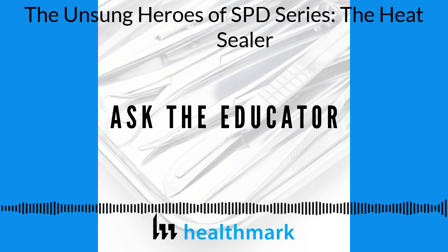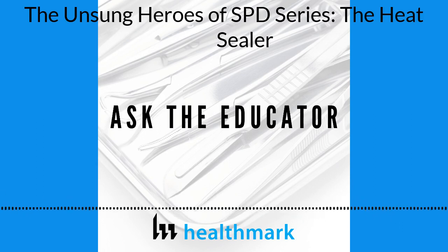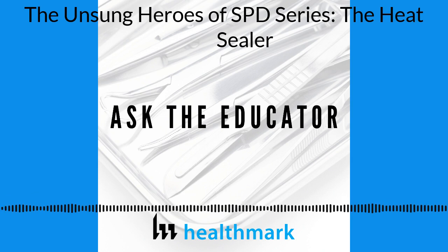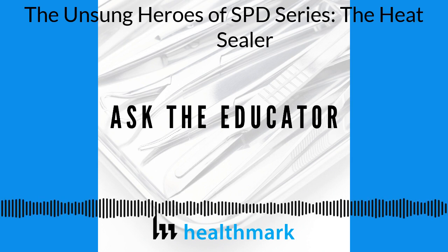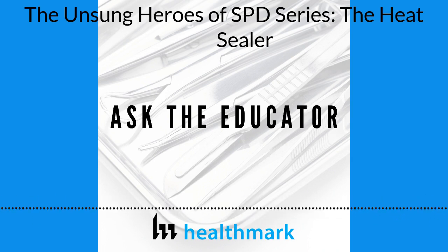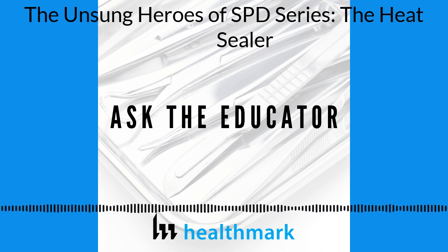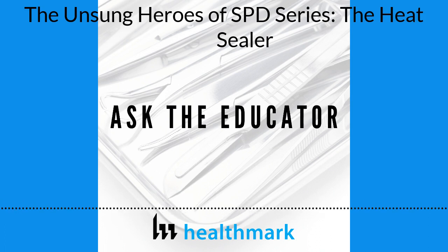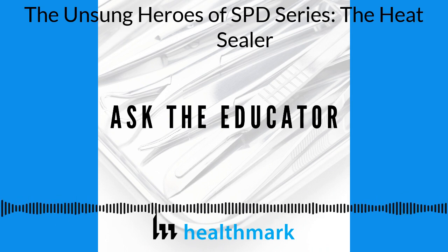All right, just to recap this episode, I spoke with Stephen Kovach about another unsung hero of SPD, the heat sealer. This device helps to ensure peel pouch items are safely secured in their sterile barrier and ready for sterilization, transport, storage, and finally use in a surgical procedure. These devices use heat, contact time, and pressure in order to produce a quality seal, and some heat sealers may use a bar with a filament as well. These are all components that could fail at any given time, which is why we should be testing this equipment each day it is in use.